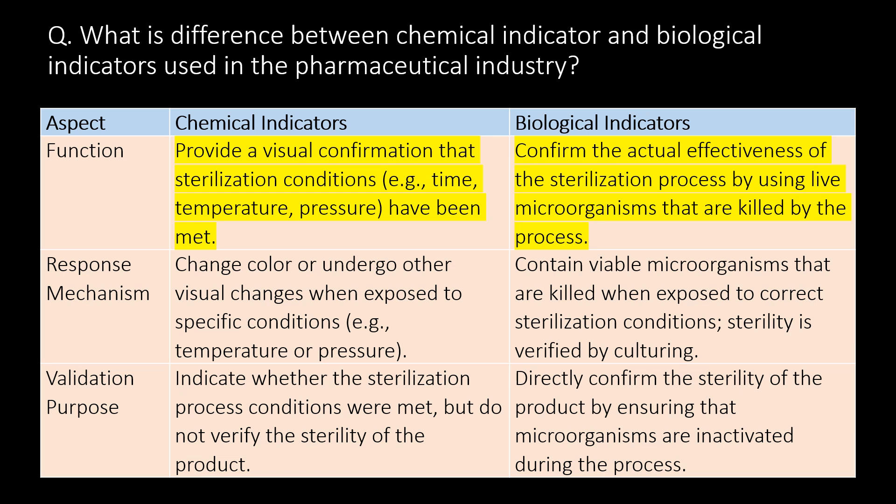A very important question: what is the difference between chemical indicators and biological indicators used in the pharmaceutical industry? You can refer to the bullet table and differentiate between chemical and biological indicators with three aspects: function, response mechanism, and validation purpose. Chemical indicators provide a visual confirmation that sterilization conditions — example time, temperature, pressure — have been met, whereas biological indicators confirm the actual effectiveness of the sterilization process by using live microorganisms that are killed by the process.